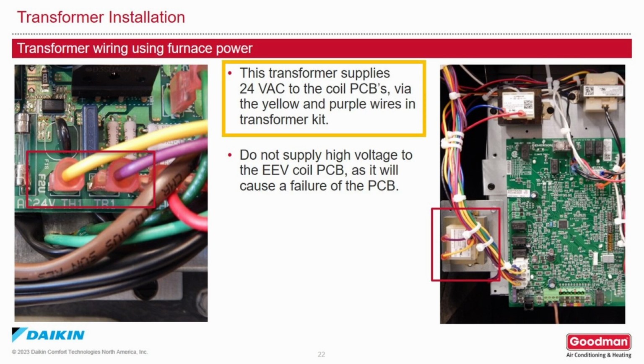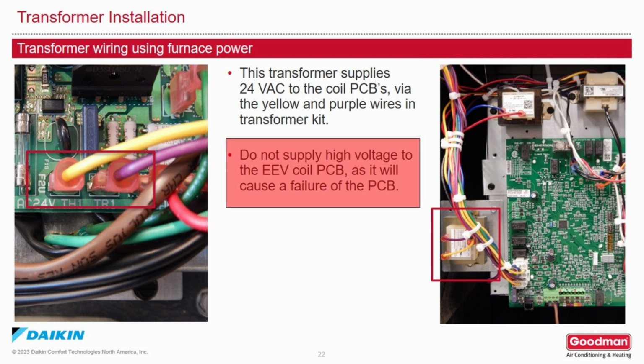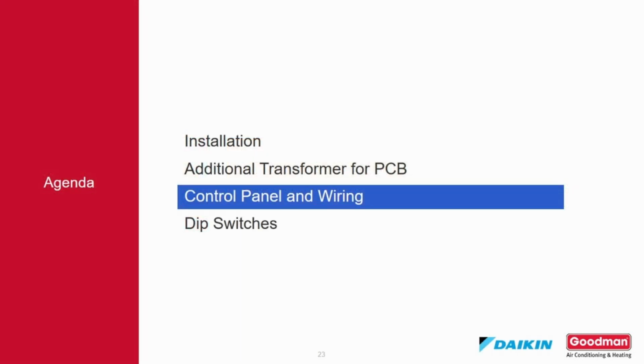This transformer supplies 24 volts AC to the coil PC boards via the yellow and purple wires in the transformer kit. Do not supply high voltage to the EEV coil circuit board. It will damage that circuit board. Control panel and wiring.